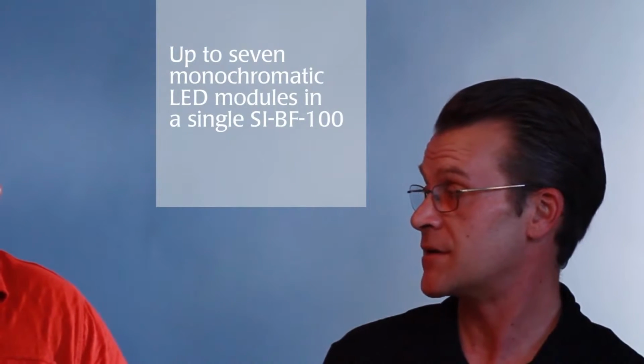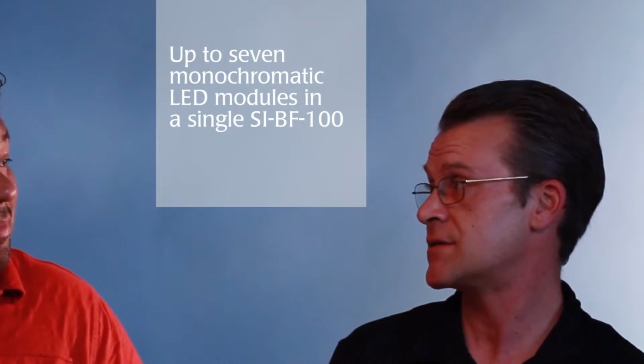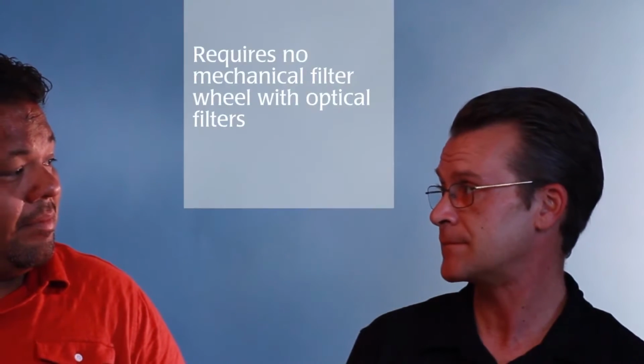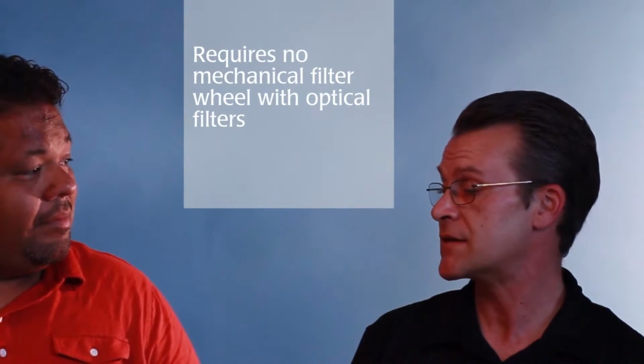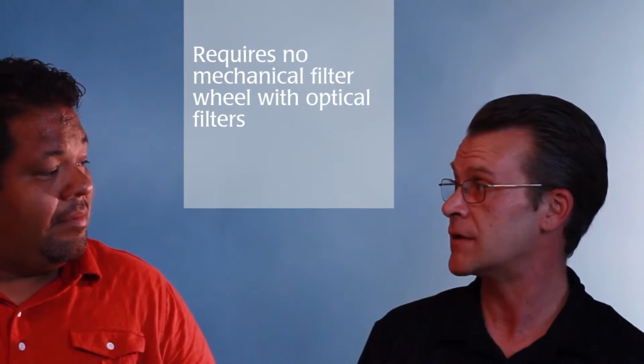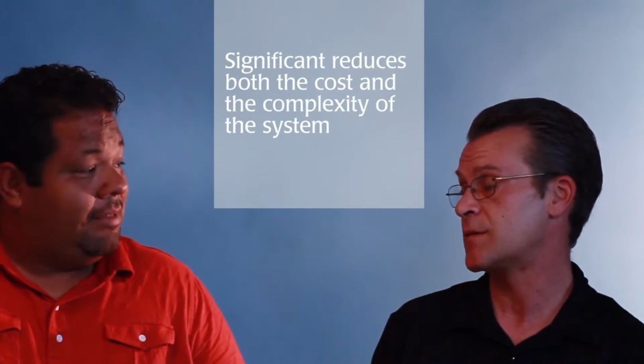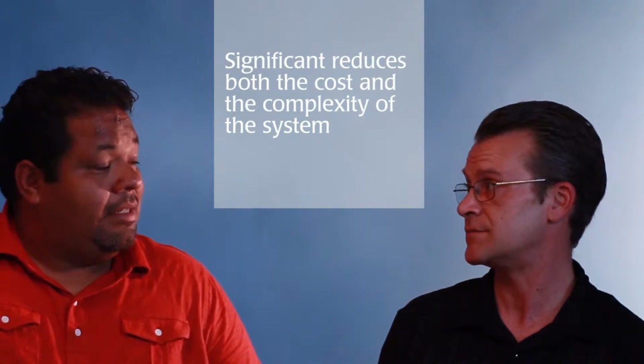How are the measurements made? The SIBF 100 can be configured with up to 7 different LED units. Each one of these LED modules is going to emit a predetermined monochromatic light. This actually eliminates the need for a mechanical filter wheel and optical filters, which is going to significantly reduce the cost as well as the complexity of the system. These are all controlled electronically, and that is the reason there are no filter wheels or filters required.